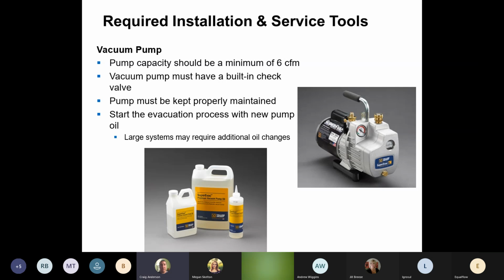Oil changes, frequent oil changes. I'm not saying to change the oil after every vacuum, but we need to constantly change the oil in that vacuum pump. That oil is what is taking in the moisture. So if you're doing a lot of jobs, you'll notice on your 10th or 12th job, why is it taking so long to pull this vacuum? Do I have a leak? Maybe your oil is full of moisture now. It can't take any more moisture in.